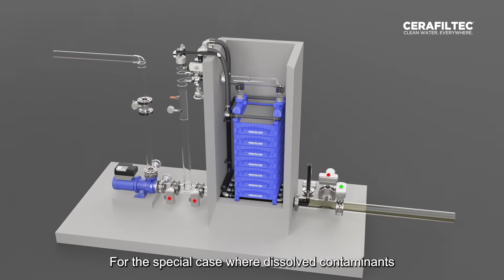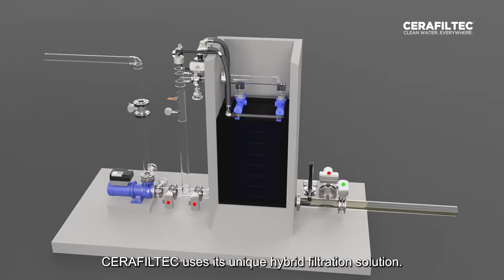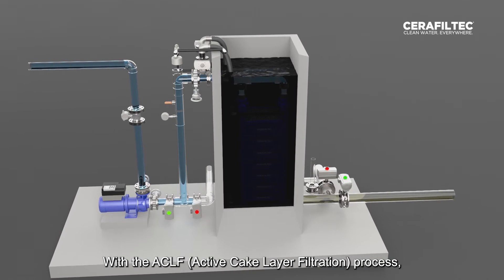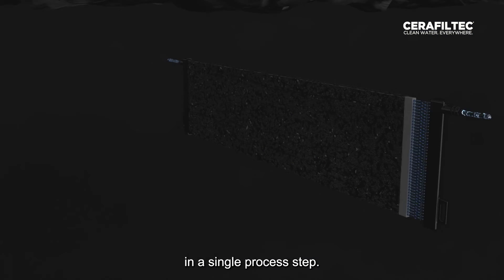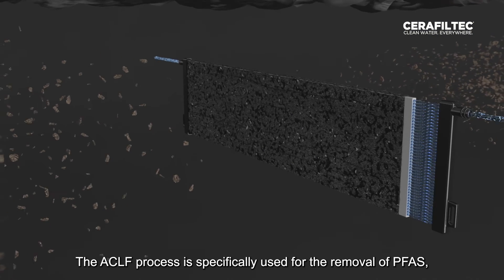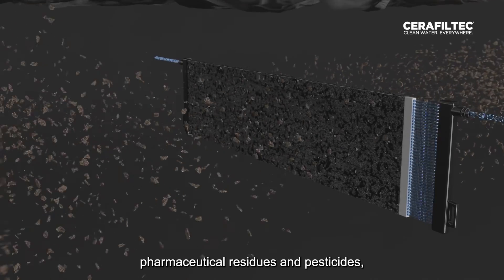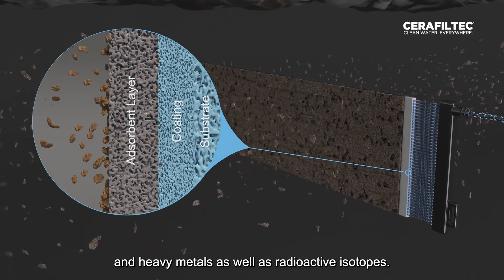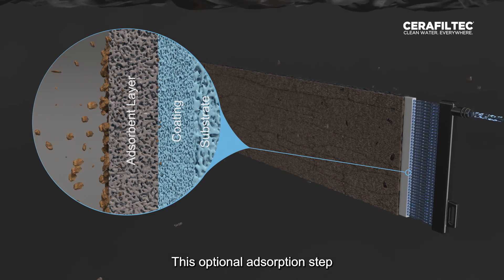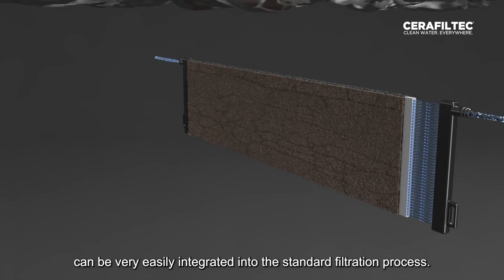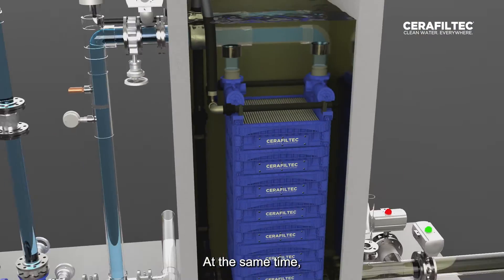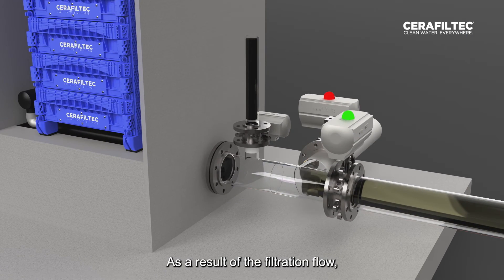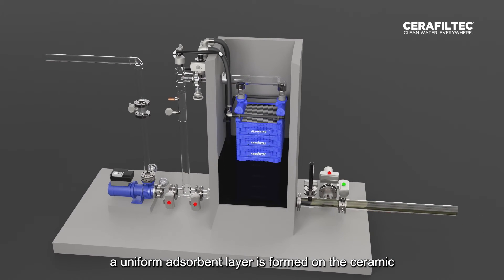For the special case where dissolved contaminants need to be removed as well, Cerafiltec uses its unique hybrid filtration solution. With the ACLF — Active Cake Layer Filtration — process, adsorption is combined with the ceramic flat membrane in a single process step. The ACLF process is specifically used for the removal of PFAS, pharmaceutical residues, pesticides, MIB, geosmin, other dissolved organic carbons, heavy metals, and radioactive isotopes. This optional adsorption step can be easily integrated into the standard filtration process. The ACLF process adds an adsorbent, such as powdered activated carbon, to the inflow, and as a result of the filtration flow, a uniform adsorbent layer is formed on the ceramic membrane surface.